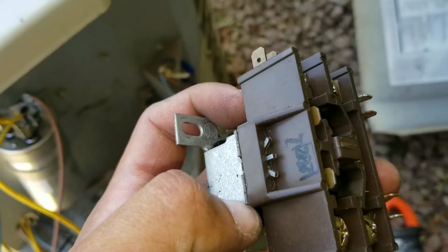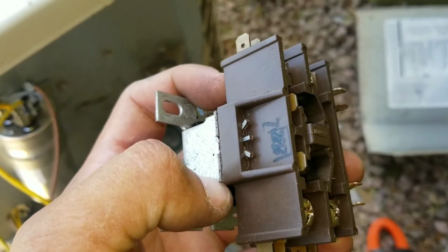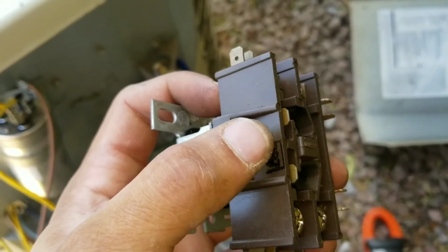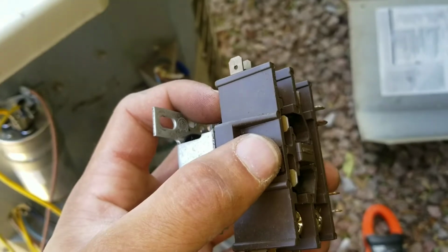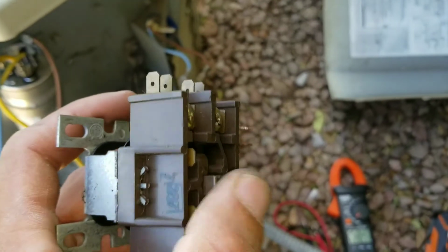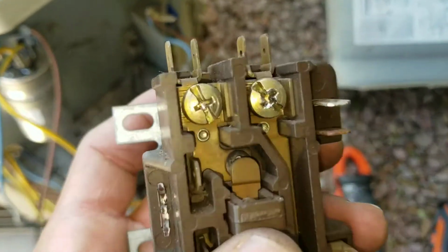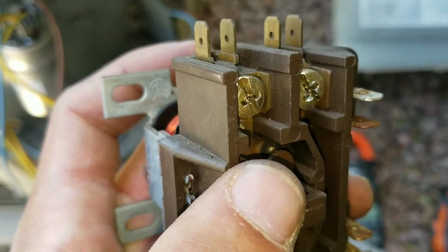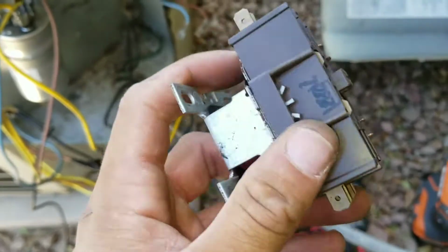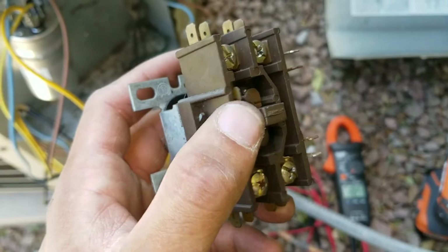Here I removed the contactor, and you can see that it's still stuck in the engaged position. I'm going to see if I can mess with it and pull on it to loosen that switch, to show you what it should look like when there's no power going to it. Here you can see I was able to mess around with it, and now it's no longer in the engaged position. And when you look, you can see it's really burnt up in the back, just all the rust and buildup. So this is probably the original contactor that's been sitting here for 20 years. So we're going to go ahead and start installing the new one.